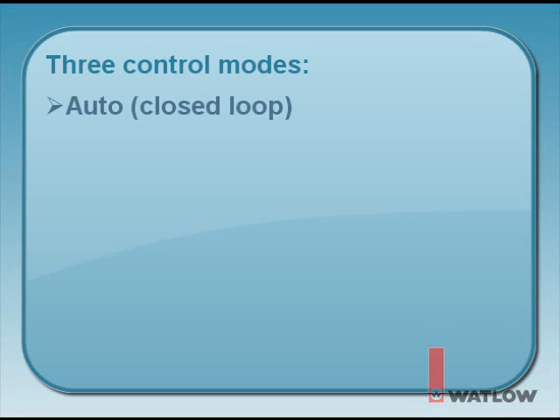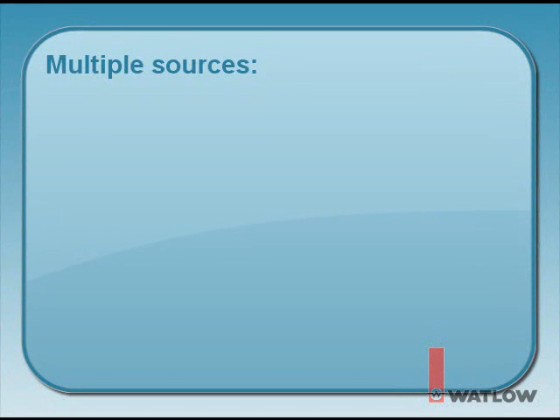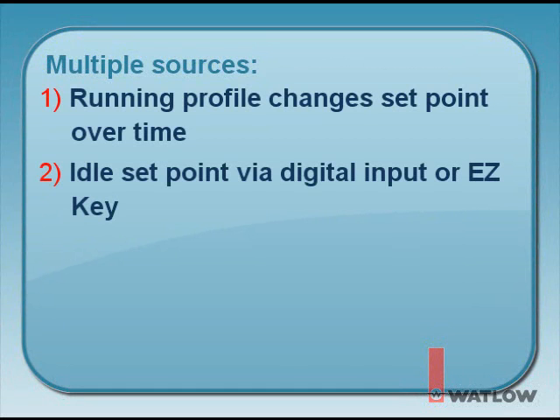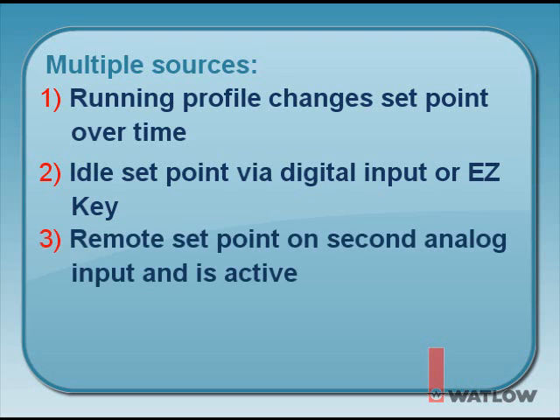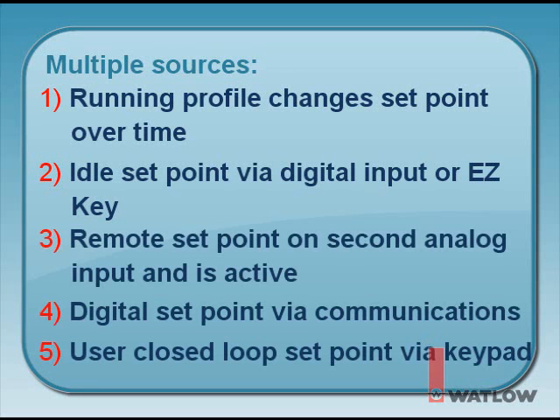In this video installment, our focus is on the auto mode. To see how to change control modes, refer to the user's manual or watch other video installments. The closed-loop setpoint used in auto mode has multiple sources for requesting the process to change value. Some of the possible sources are: a running profile programmed to change the setpoint over time; an idle setpoint requested via digital input or an EZ Key; a remote setpoint fed to the controller using a second analog input; a setpoint generated and sent using communications from a PC or PLC; and most commonly, the user requests a closed-loop setpoint using the keypad.